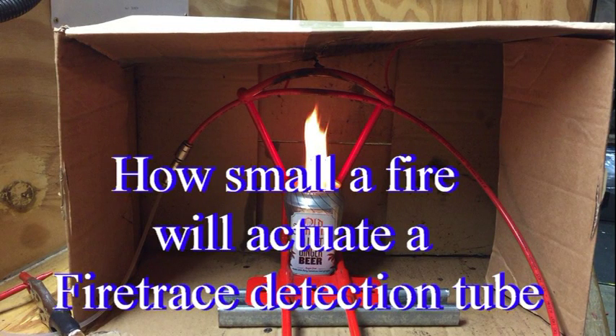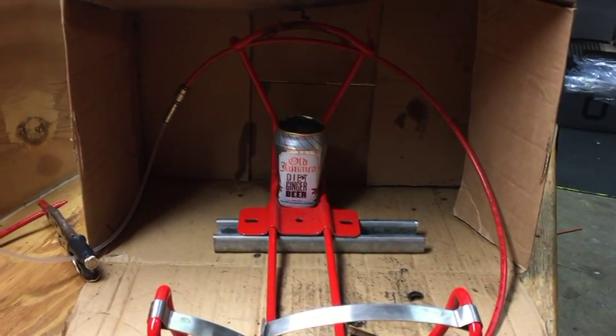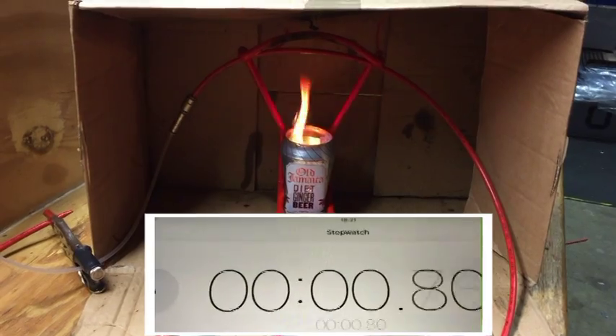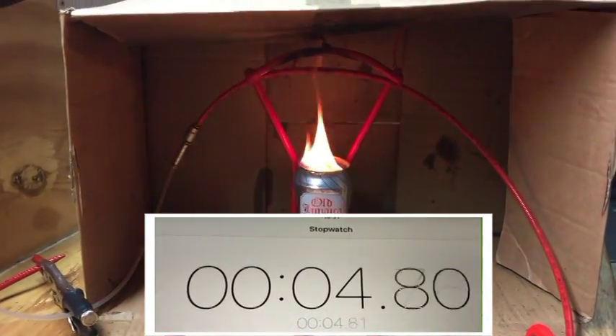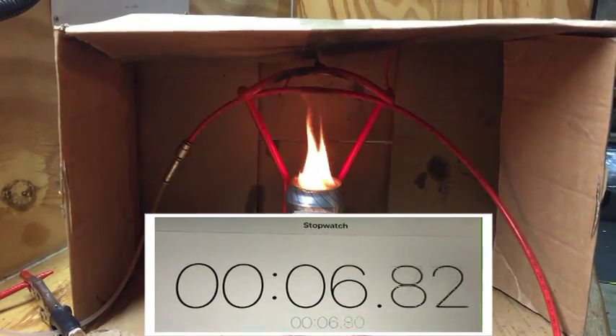The amount of energy produced by a fire is relevant to the amount of fuel involved, the time of burn, and the proximity of the detector. For this experiment, I have used five grams of four-star petrol. The automatic Firetrace detection tube is placed 100 millimeters above the fire.